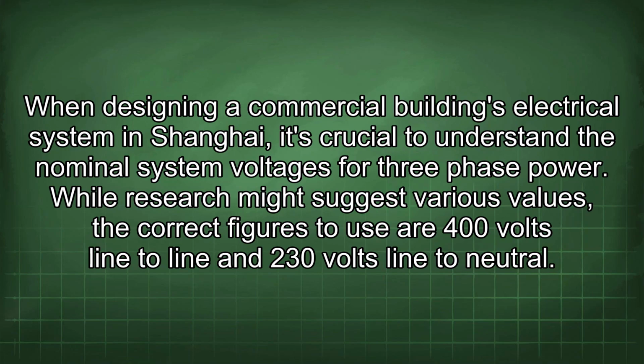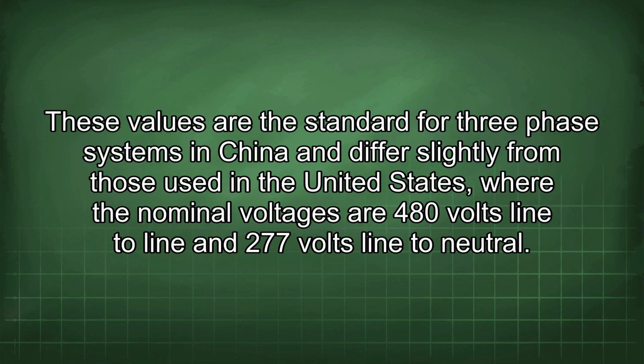When designing a commercial building's electrical system in Shanghai, it's crucial to understand the nominal system voltages for three-phase power. While research might suggest various values, the correct figures to use are 400 volts line-to-line and 230 volts line-to-neutral. These values are the standard for three-phase systems in China and differ slightly from those used in the United States, where the nominal voltages are 480 volts line-to-line and 277 volts line-to-neutral.